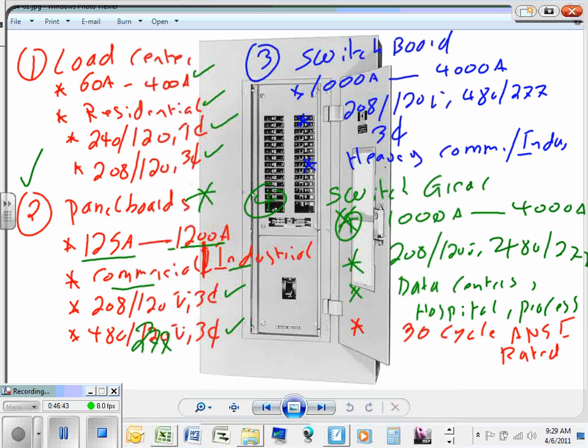In our system, most of them are going to be 480/277, except one panel. It's going to be 208/120. Anybody remember that panel? Receptacle panel. If you were to design this system in Europe, Brad, not that you're so excited about Europe, you only need one voltage. 380/220, one panel, receptacles at 380/220, lights 380/220, mechanical equipment 380/220. So you don't have 208/120. That's kind of the advantage of having a higher voltage, but it is what it is.